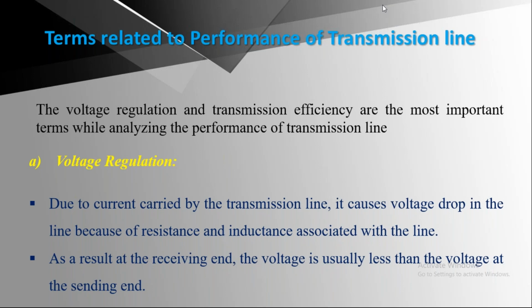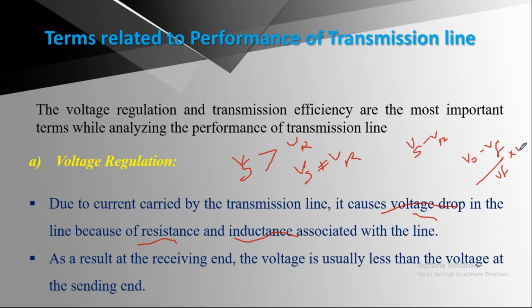So because of this, the sending end voltage is not equal to the receiving end voltage, due to the voltage drop caused by resistance and inductance associated with the line. As a result, at the receiving end, the voltage is usually less than the voltage at the sending end. So the sending end voltage is greater than Vr. So the voltage regulation formula is Vs minus Vr, that is no load voltage V0, divided by Vf, into 100.